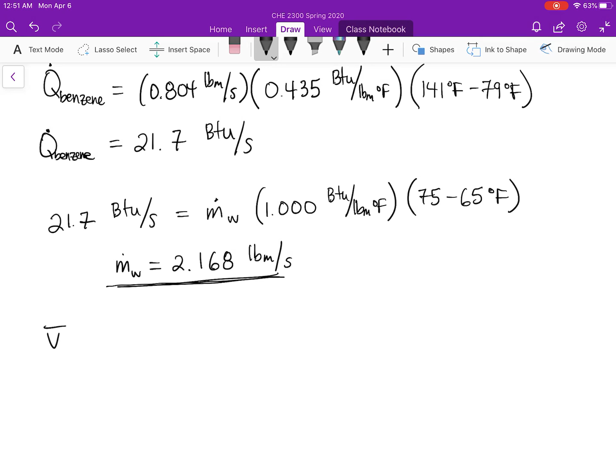The mass flow rate of my water is 2.168 pound mass per second, divided by that cross-sectional area, which can be calculated to be 0.00997 feet squared, and multiplied by the density of my water at my bulk temperature, 62.3 pound mass per foot cubed. Carrying out that calculation, I get an average velocity of my water of 3.49 feet per second.